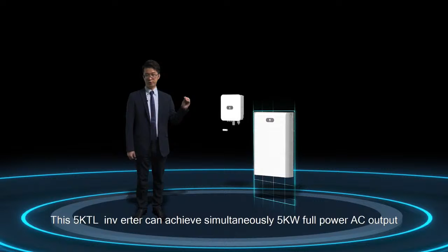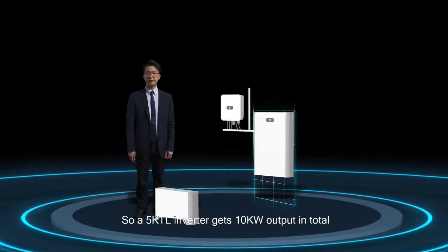Another great feature is the dual power battery ready feature. So for homeowners who purchase the 5 kTL Huawei residential inverter, if adding 10 kilowatt PV on rooftop with the help of Huawei optimizer long string design, this 5 kilowatt inverter can simultaneously achieve 5 kilowatt full power AC output plus 5 kilowatt full power battery charge. So a 5 kilowatt inverter can get 10 kilowatt in total. It's a very cost-effective deal.